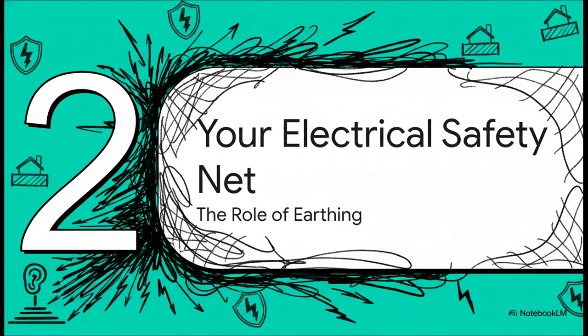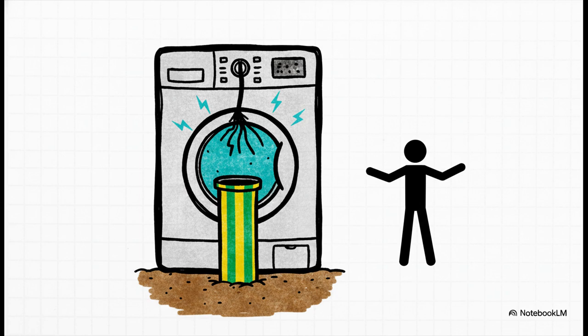Okay, so we've got the problem, now what's the solution? Let's meet the hero of our story, the electrical safety net itself. This is all about the fundamental role that earthing plays. The easiest way to think about it is like an emergency overflow drain for electricity. If there's a leak, that fault current, the earthing system gives it a super easy, safe path straight to the ground. This prevents the metal casing of your appliance from becoming live.